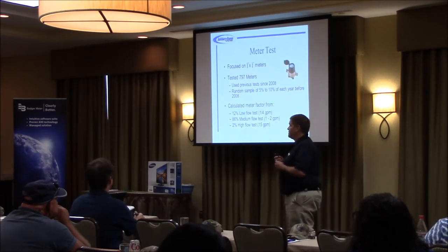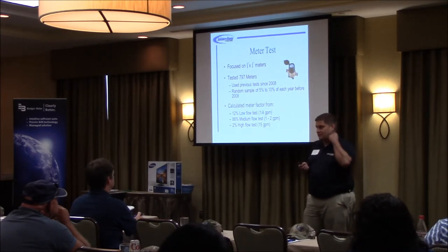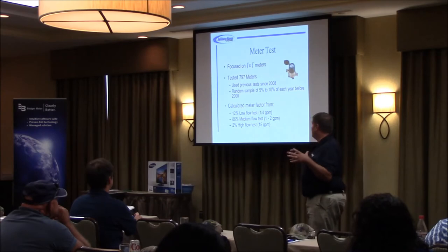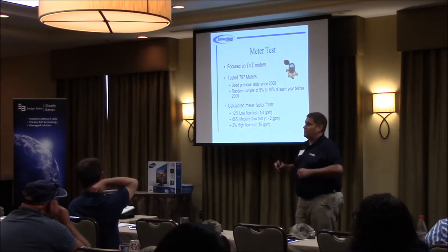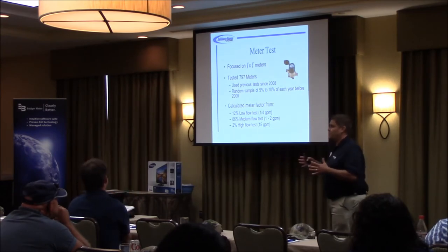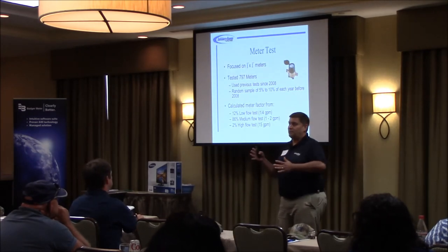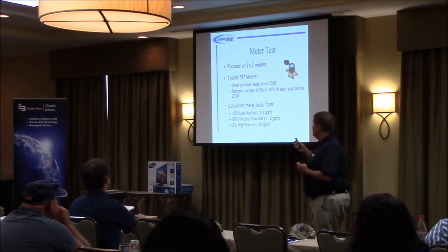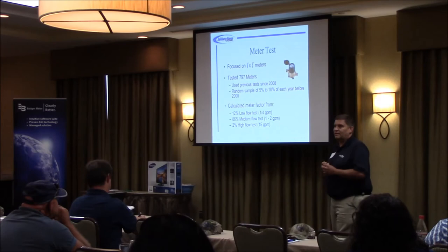So what we did was we focused on our 5/8 by 3/4 meters, got our meter techs together, and put together a test of 800 meters, so that we had a large sample. We used tests that they had done since 2008. At the time, these were about 3 or 4 years old, which was how far back we went. So we pulled a lot of records, and we didn't have to test a full 800 meters. Then we did a random sample of meters, 5 to 10% out of each year prior to that.